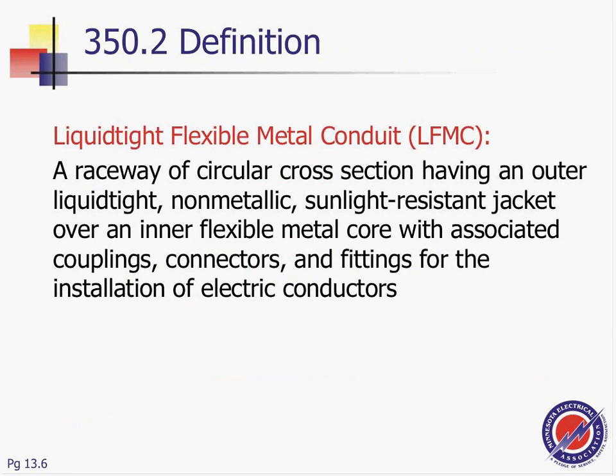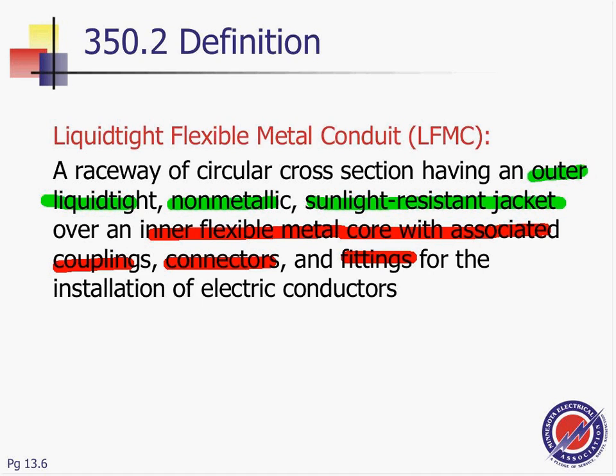Now, what is this? It's a raceway, circular in cross-sectional area. This is really the change from up to this point. Up to this point, we're really describing a flex. Here, an outer Liquidtight, non-metallic, sunlight-resistant jacket. That's it. That's what makes it Liquidtight, as we all know. Over the inner flexible metal core with associated couplings, connectors, and fittings, for the business of electrical wires, not for gas or anything else. So the point, guys, is that the outer non-metallic, sunlight-resistant jacket really makes it tight in terms of water. Liquidtight. Anything else about this? So you don't want the water to get in. Liquidtight flexible metallic conduit.